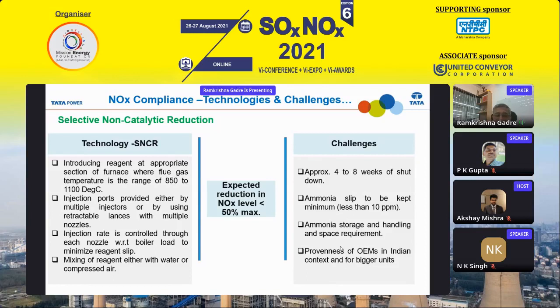NOx also depends on the coal. If somebody is burning difficult coals, especially Indian coals which are very difficult from the NOx point of view, they may require SNCR. And if they do, dealing with ammonia slip and huge quantities of ammonia will be a difficult situation from the environment and safety point of view.